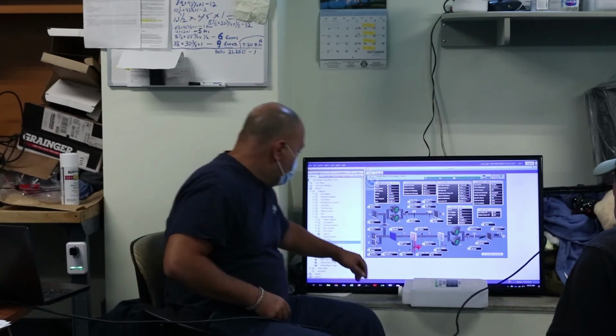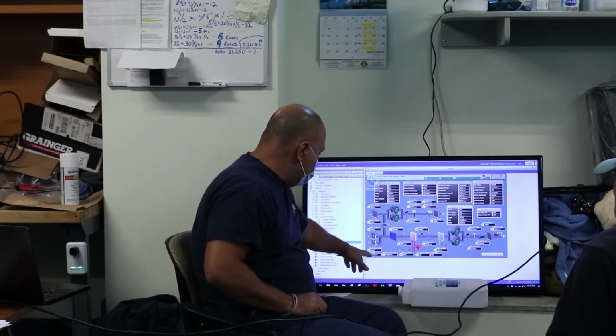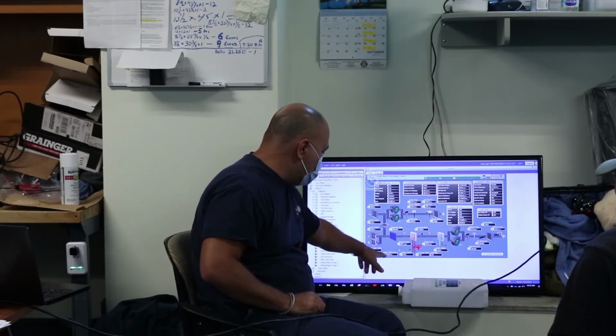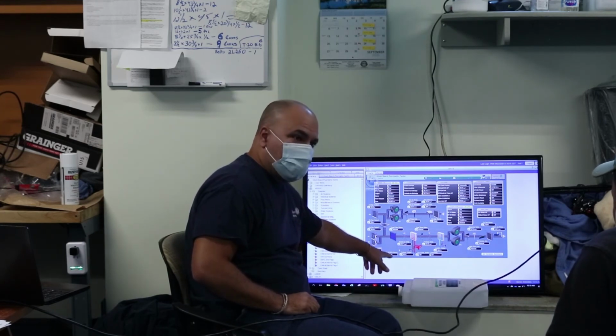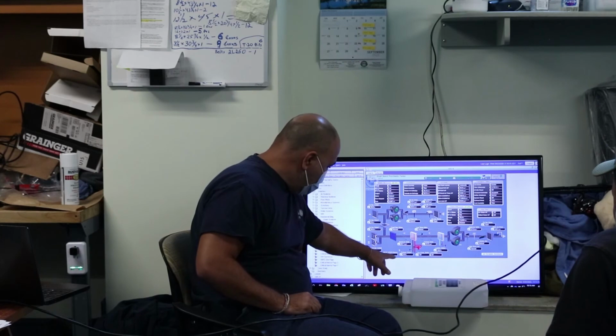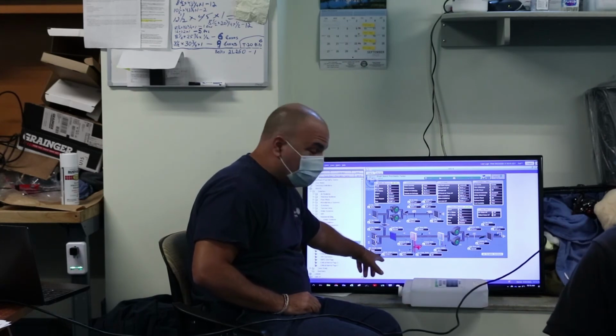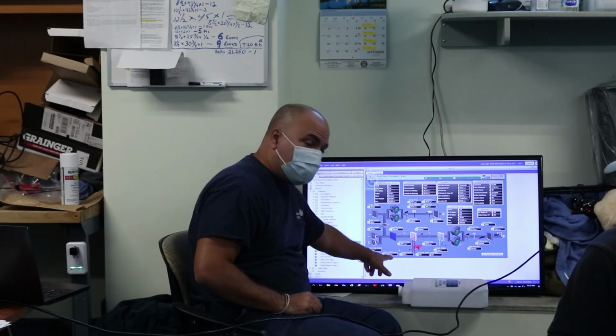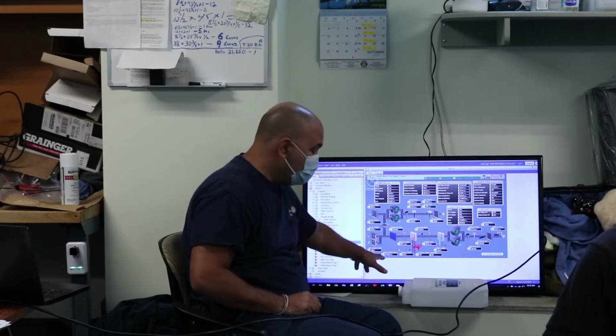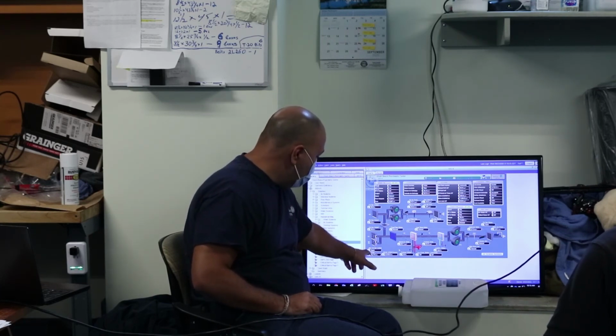So we're going to look to maintain. Here's the minimum outside airflow set point, and in parentheses is what the spec calls for. So you're looking for 8,500. That is adjustable. I'm just telling you what it was designed for. You guys can adjust that later on if you want.